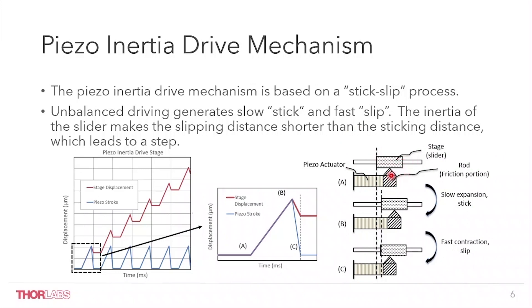The friction rod has one end connected to the piezo actuator and one tip contacting the slider, so the rod can be pushed or pulled by the piezo actuator.